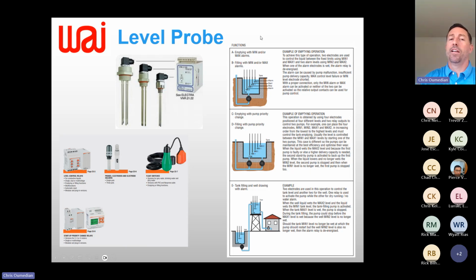These are discrete output, simple devices. Something like this can be used in a little bit of a dirty media because you've got conductive probes, as long as the media doesn't stick to your probes where it would get gummed up. The other technology that we use would be basically float switches. So think of the float in the tank of your toilet or your pool autofill. As that thing goes up, you've got a mechanical switch when the water level gets there, and it's going to give you a discrete or a relay output that says my tank is too high, my tank is too low, or I'm at some midpoint that I want to monitor.